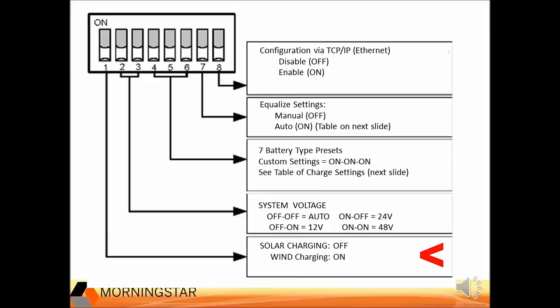All the factory presets are managed with switches four, five, and six, regardless of whether it is in solar or wind mode. The wind mode is only available for the TriStar MPPT 150-volt controller at this time, not the 600-volt controller, and it is not in the TriStar MPPT manual yet. If there is no other information yet available regarding the wind feature on the website or updated manual, please contact Morningstar support for more information on the wind feature.